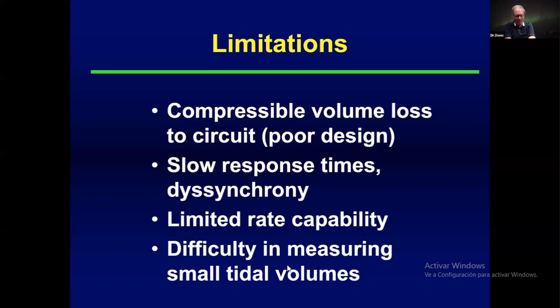Number one, compressible volume loss. The circuits were very poorly designed in those days. They were nothing more than corrugated cardboard covered by a rubber coating. So they were super compliant. Well, you can imagine what would happen if you discharged a high pressure breath from the ventilator. You'd watch the ventilator circuit billow beautifully, but the baby's chest wouldn't rise at all. The device had a very slow response time, often resulting in dysynchrony. By today's standards, it had a very limited rate capability. It also had a major drawback in that we had extreme difficulty in measuring small tidal volumes. We didn't have today's wonderful transducers.